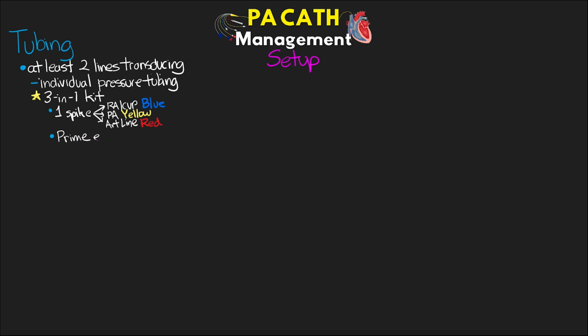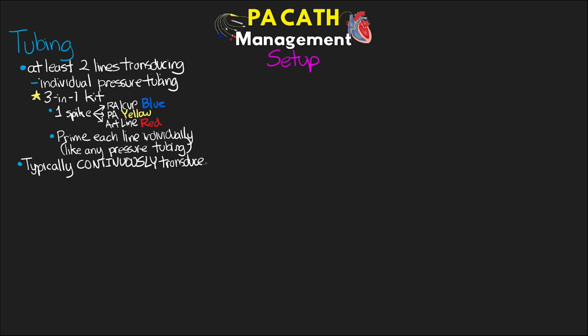Now with these, we still prime each line individually the same way that we would do any other pressure tubing. And then typically we're going to be continuously transducing the RA CVP and the PA lines. Now the pulmonary capillary wedge pressure is obviously something that's obtained intermittently with the inflation of the balloon, assuming that your facility allows you to do this. Now we could intermittently do the RA CVP line, but at a minimum, the PA line must always be transduced.